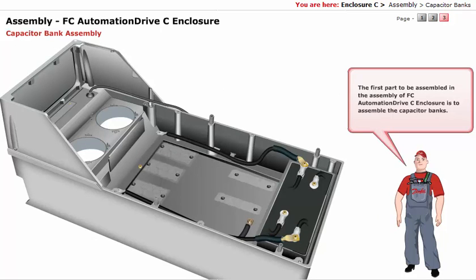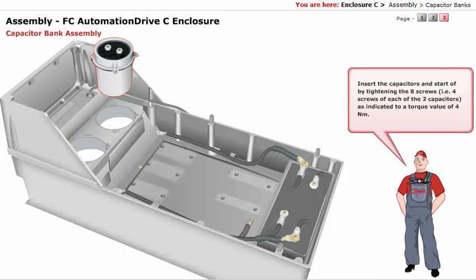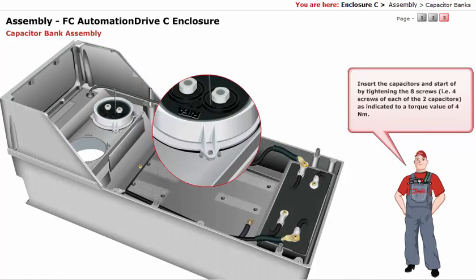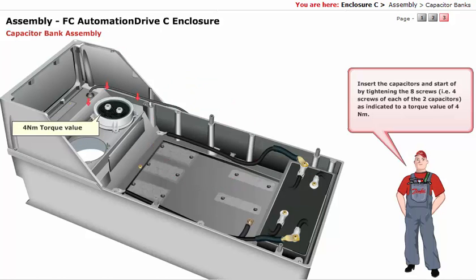The first part to be assembled in the FC AutomationDrive C Enclosure is the capacitor banks. For C1, there are two capacitors. Insert the capacitors and start by tightening the eight screws — that is, four screws of each of the two capacitors — as indicated, to a torque value of 4 Nm.